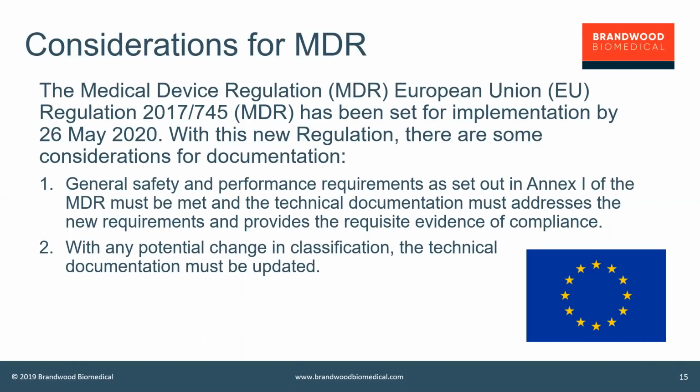Yeah, so with the exception of the actual regulatory pathways themselves, and we can get into that in a second, I think this is where, again, you kind of play to the highest classification in the creation of your technical file. So what I mean by that is, if let's say your device is being up-classified by the MDR to a class 3, but it remains a class 2 in the US or Europe or excuse me, Australia or Canada or whatever, you would want to make sure that your documentation, the overall technical file supports that higher classification.